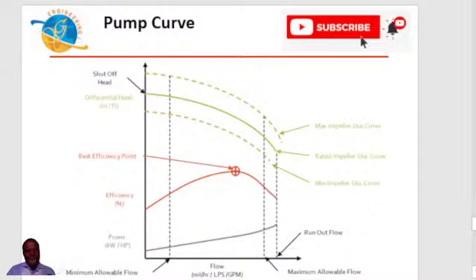Usually when a pump manufacturer furnishes you with a pump curve, it comes with 3 impeller diameter curves: the maximum impeller diameter curve, the rated impeller diameter curve, and the minimum impeller diameter curve.